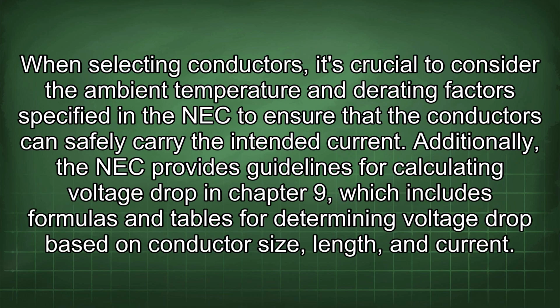When selecting conductors, it's crucial to consider the ambient temperature and derating factors specified in the NEC to ensure that the conductors can safely carry the intended current. Additionally, the NEC provides guidelines for calculating voltage drop in Chapter 9, which includes formulas and tables for determining voltage drop based on conductor size, length, and current.